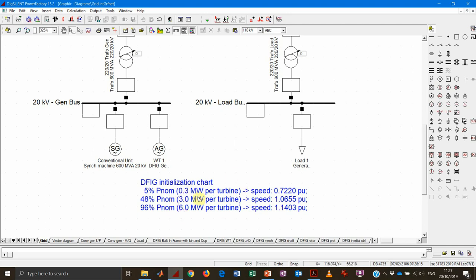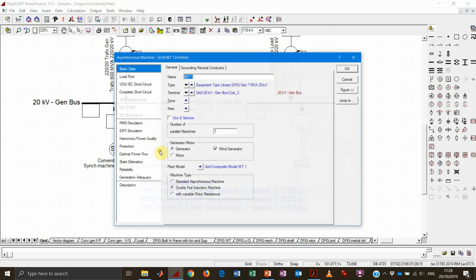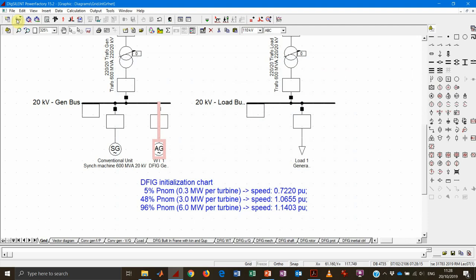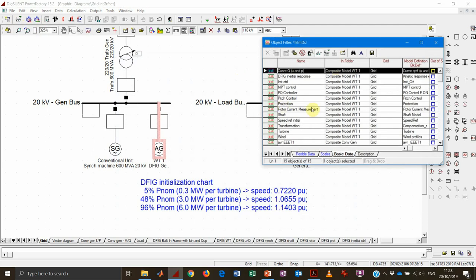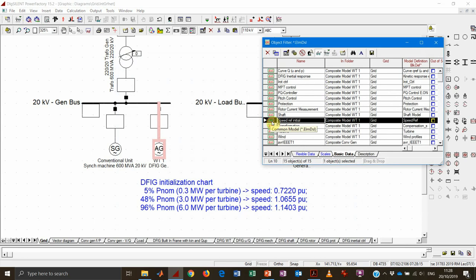The most common power set points used in this course are: 0.3 megawatt, corresponding to approximately 5% of initial power; 3 megawatt, approximately half of nominal production; and 6 megawatt, almost full production. For each initial power we need to specify the initial rotational speed inside the dynamic model — not the wind speed, but the normalized rotational speed of the generator. The initial power is set in the load flow page of the element, while the initial rotational speed is specified in the 'speed ref initial' block.